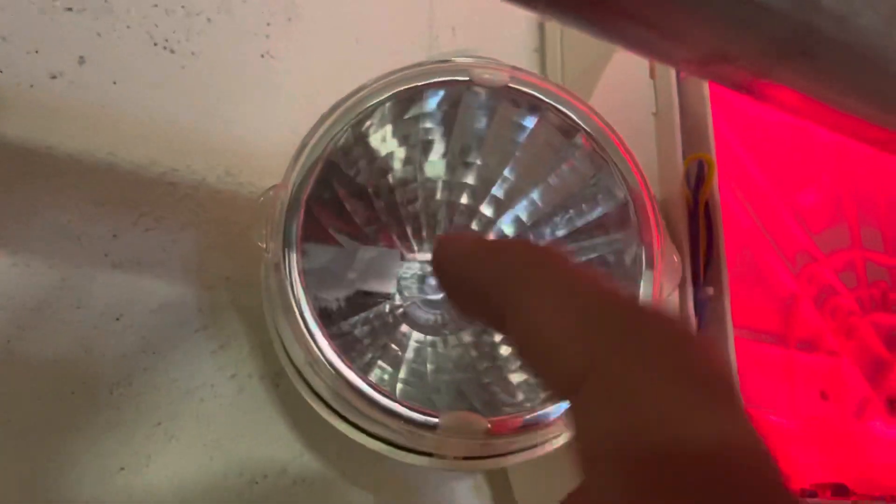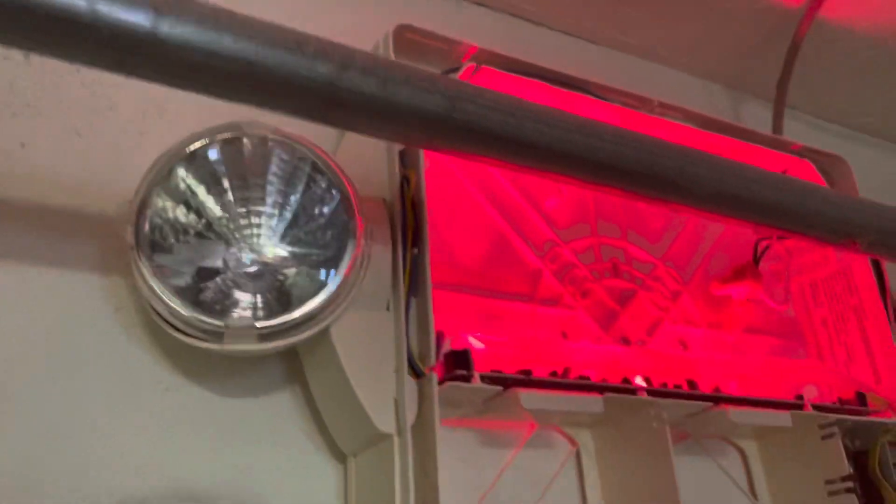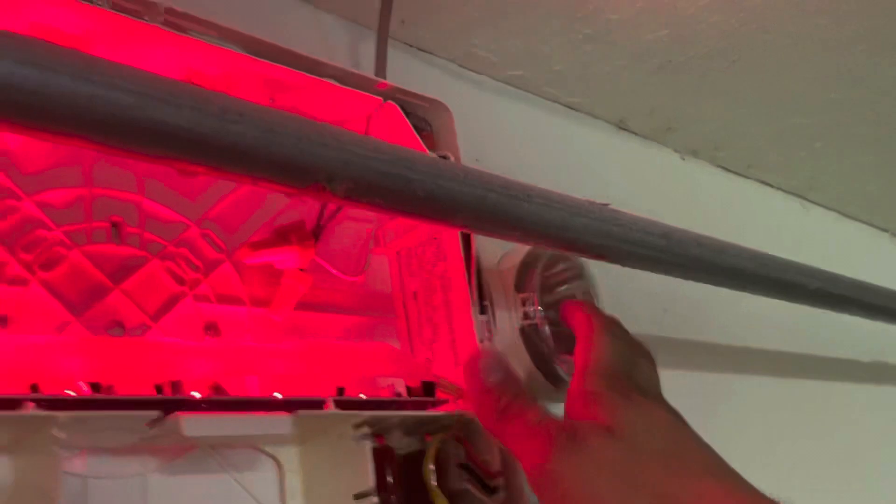Here's what these signs look like on the inside. Right here is the main power board. Here is the LED board, charger board, and what controls the switch from emergency lighting to battery — from normal operation to battery backup. Here's where the emergency lights hook up. This is not a high-capacity unit, so you can only hook up two of them — one, two.